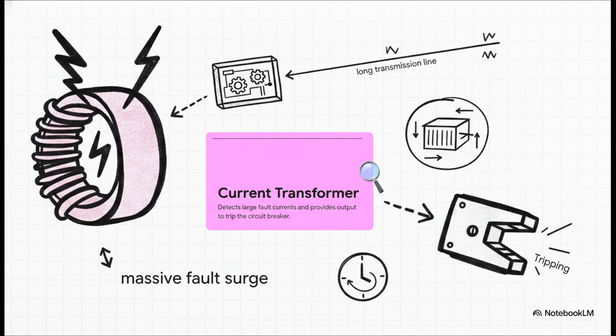Second, we have distance relays, which are heavily used on transmission lines. They calculate impedance to figure out the distance to the fault, using layered zones. Zone 1 covers most of the line and trips instantly, while zones 2 and 3 cast a wider net and trip with a slight delay to act as a backup. Finally, differential relays. These protect a very specific zone, like a transformer, by comparing the current entering versus leaving. If those numbers don't match exactly, it means there's an internal fault, and it trips instantly with zero delay. It's the fastest, most secure scheme available. You just have to match the scheme to the zone size and speed requirement.